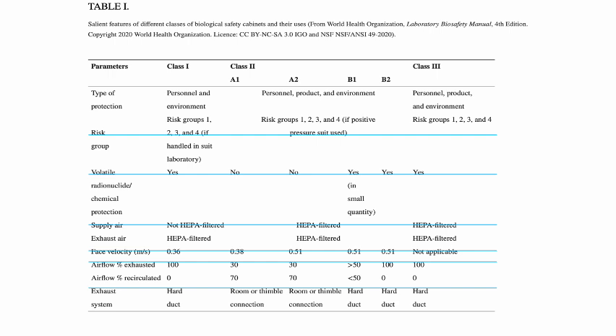Now, in terms of risk groups that you can handle in the different classes of biosafety cabinet: for your Class 1, you can handle risk groups 1, 2, 3, and 4. Risk groups 3 and 4 are allowed if you are in proper PPE, usually if the personnel is in a suit laboratory. If you are not in proper PPE, you can only handle risk groups 1 and 2 in Class 1. In Class 2, you can handle risk groups 1, 2, 3, and 4. It can go up to 4 provided that you are in a positive pressure suit. If you are not in a positive pressure suit, you can only work up to risk group 3 in a Class 2 biosafety cabinet.